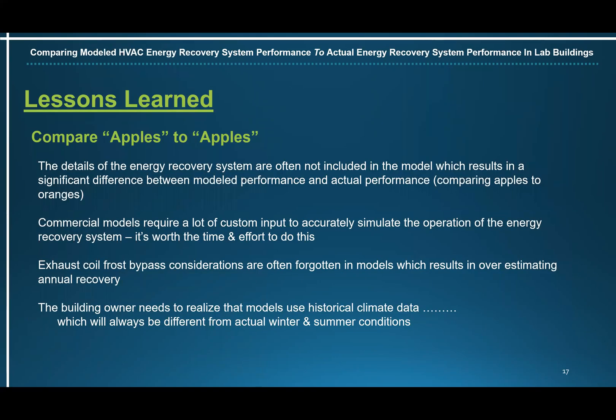Lessons learned. Compare apples to apples — the details of the energy recovery system are often not included in the model, which results in a significant difference between model performance and actual performance. Commercial models require a lot of custom input to accurately simulate the operation of the energy recovery system, and it's worth the time and effort to do this. Exhaust coil frost bypass considerations are often forgotten in models, which results in overestimating annual recovery. The building owner needs to realize that models use historical climate data, which will always differ from actual conditions.